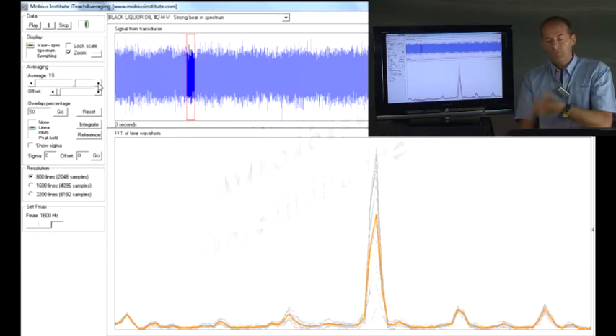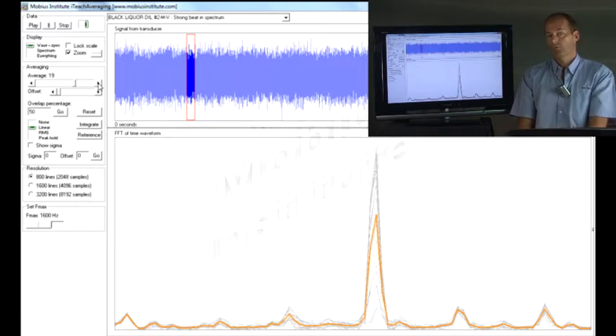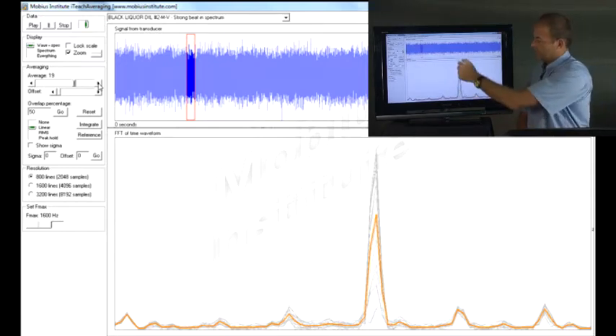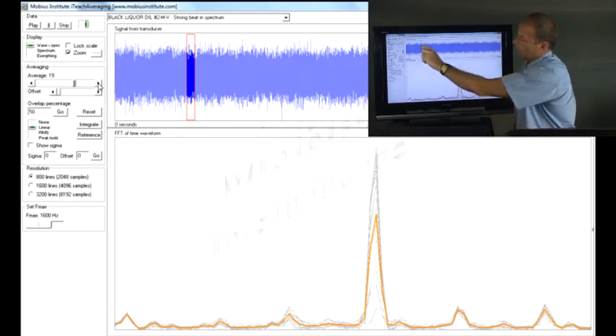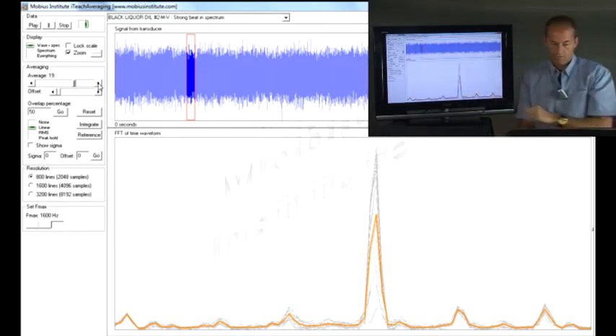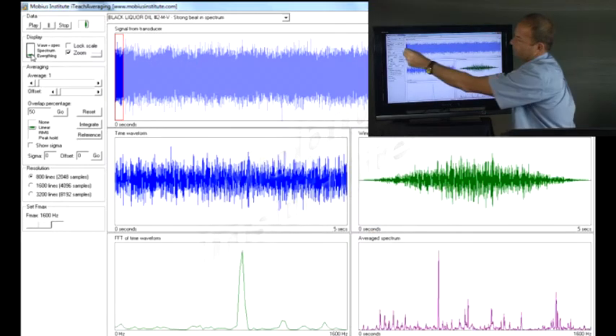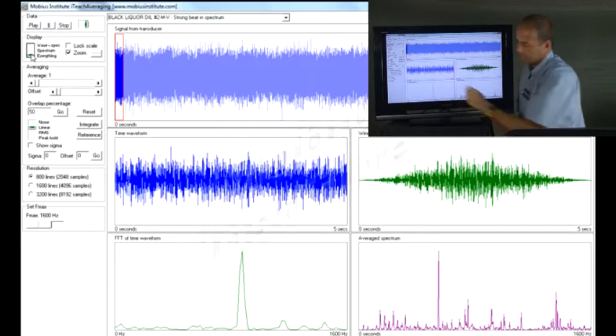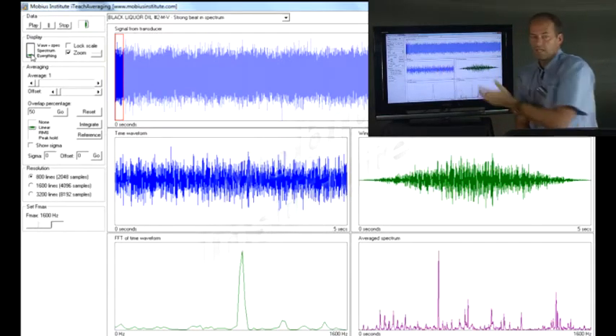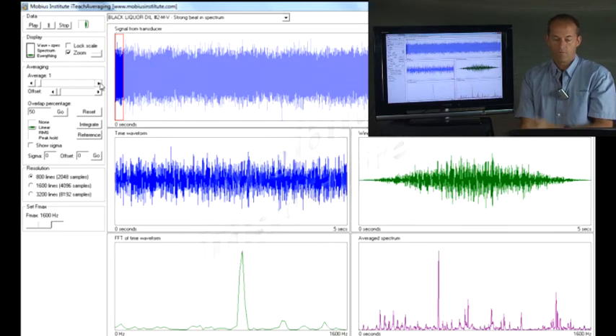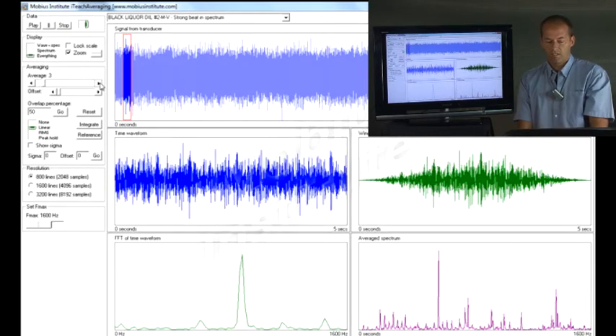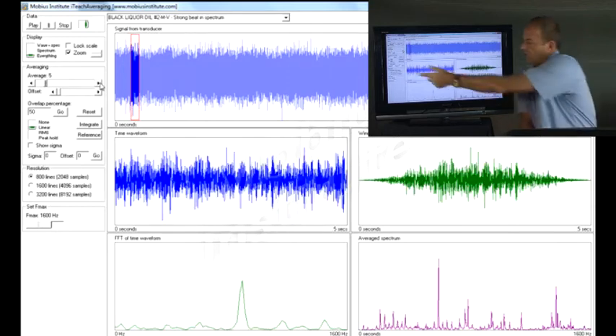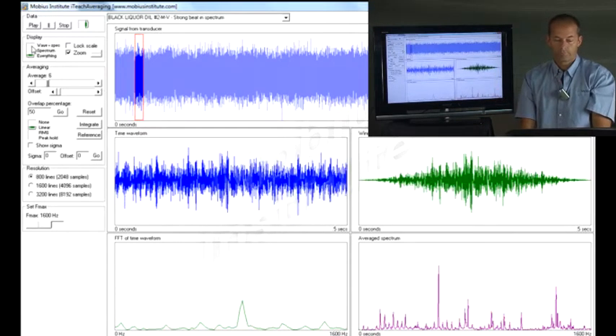So if we use enough averages, we will end up with something that's repeatable, but we have no idea that this bounced up and down. And because this waveform here, this little chunk of time here is what we see there. This is the time waveform you would get if you ask for time waveform as part of your data. You could never tell there was any beating going on just by looking at this time waveform.